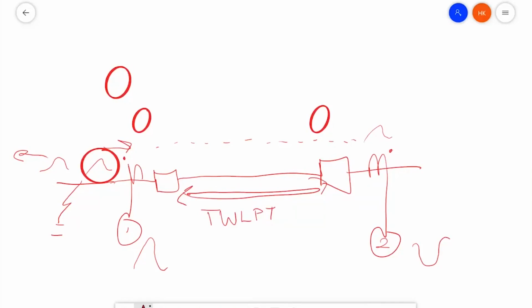So another good indication of an external fault is that the wave enters the CT at t equals 0, and we expect it to exit the line, and relay number 2 will see it, in the traveling wave line propagation time that we have told the relay. And that's something that you can measure. There is a way to calculate it in our manuals, but the best way to do it is to measure it, and we have application guides that show how to measure this traveling wave line propagation time.